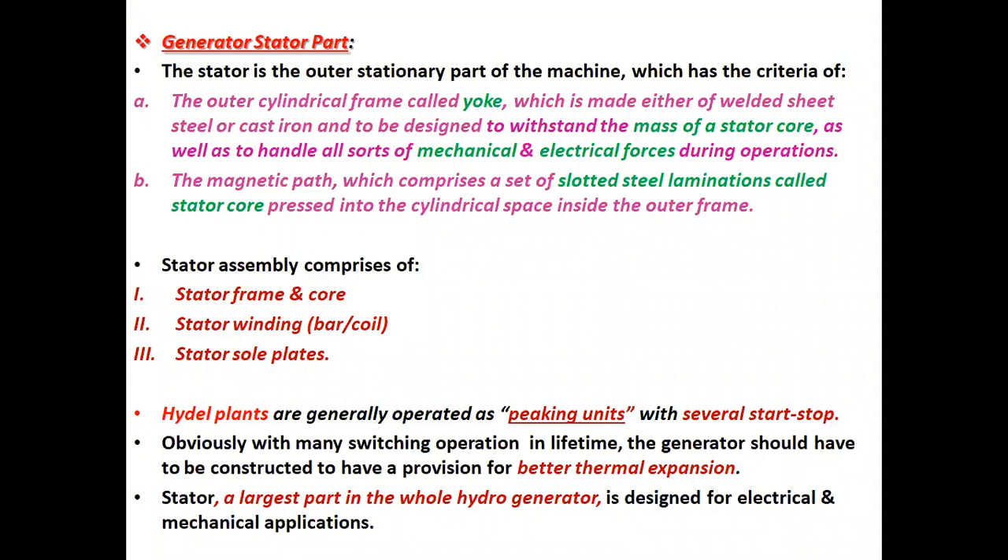The stator is the outer stationary part of the machine, which has the following criteria: A, the outer cylindrical frame called yoke, which is made either of welded steel or cast iron and designed to withstand the mass of stator core, as well as to handle all sorts of mechanical and electrical forces during operation. B, the magnetic path, which comprises a set of slotted steel laminations called stator core, pressed into the cylindrical space inside the outer frame. Stator assembly comprises of: one, stator frame and core; two, stator winding, that is bar winding or coil winding; and three, stator sole plates.